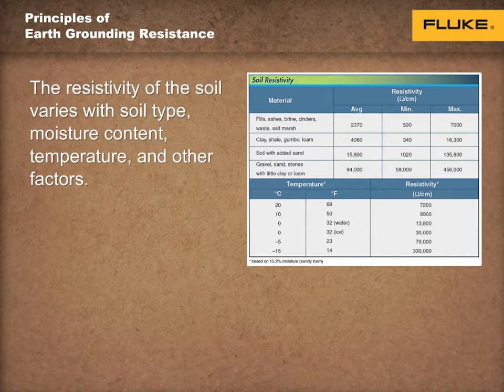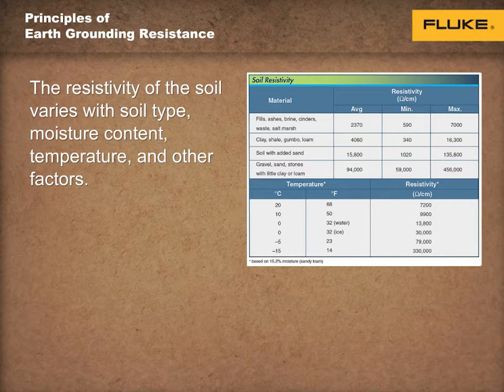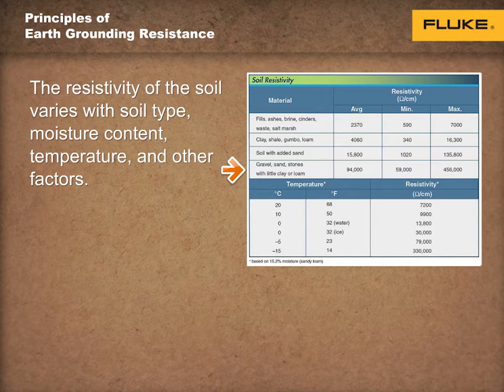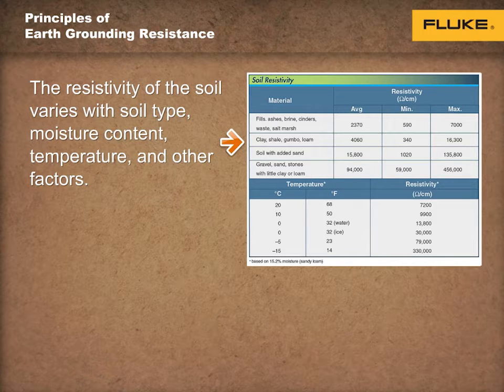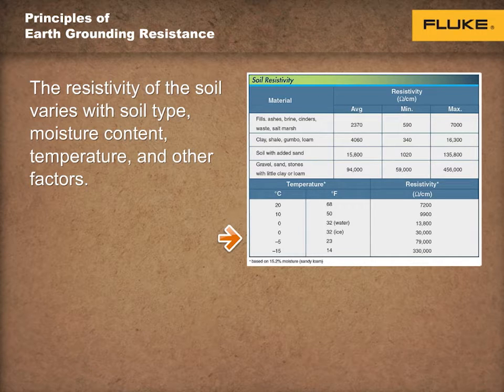The resistance of the earth, or soil, always varies with soil type, moisture content, temperature, and other factors. Typically, sand and gravel conduct poorly, and clay conducts much better. Although more soil moisture lowers resistance, which allows better conductivity, resistance increases when the soil freezes.